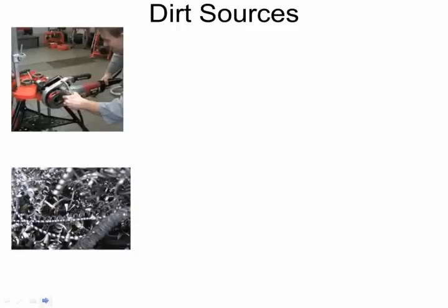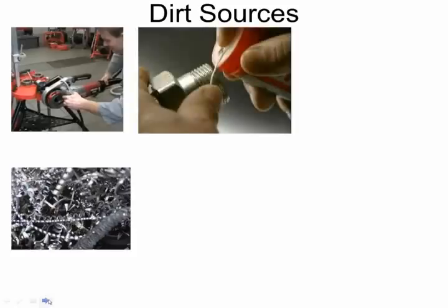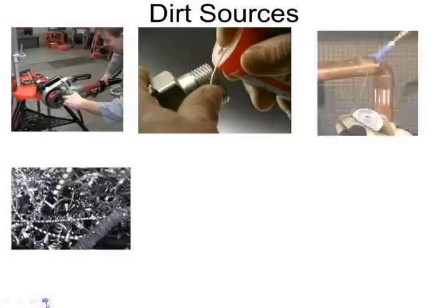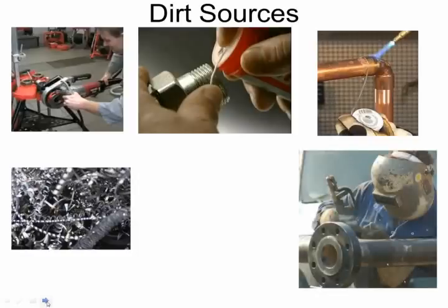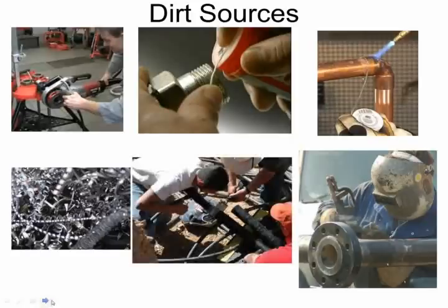Well, it could come from the fabrication process on site. We might want to cut some threads in our pipe, which is commonly done, create some shavings. Those could get into the system. Pipe tape, pipe string, pipe dope, other materials could get into the system. We've seen those here back at the offices in Milwaukee on products that are returned sometimes. The soldering process, you can end up with solder in your piping. On the commercial jobs, you can actually get some weld slag into the system. Well, none of these are really dirt. Probably it should be a "you don't want it there" type slide rather than say dirt.